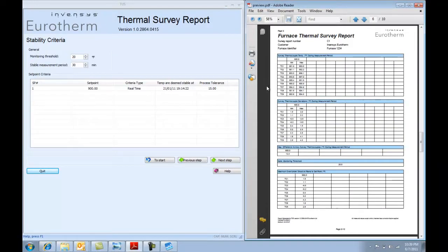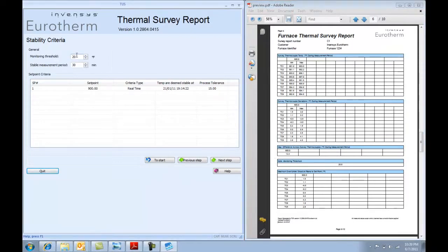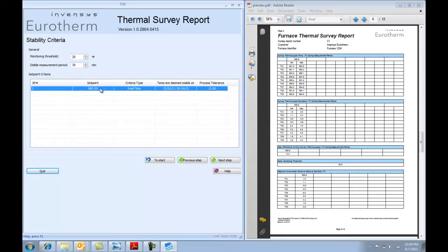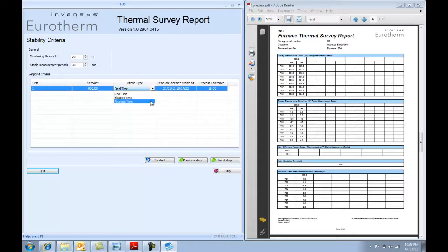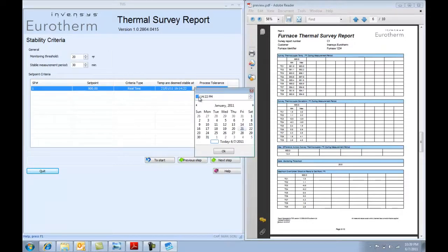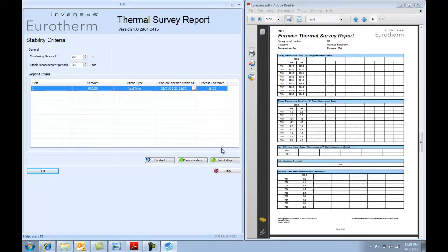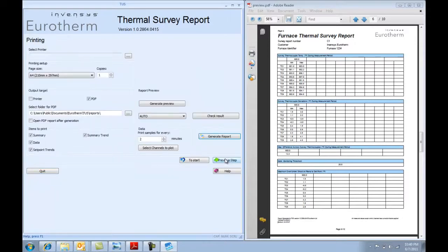Here, this is where you're setting when you're monitoring the thermocouple data. So this is 20 degrees Fahrenheit before you hit the set point and you're running for 30 minutes. You can monitor through an automatic analysis or more generally through real time and setting the time and date that you want to actually start your minimum 30 minutes soak time.